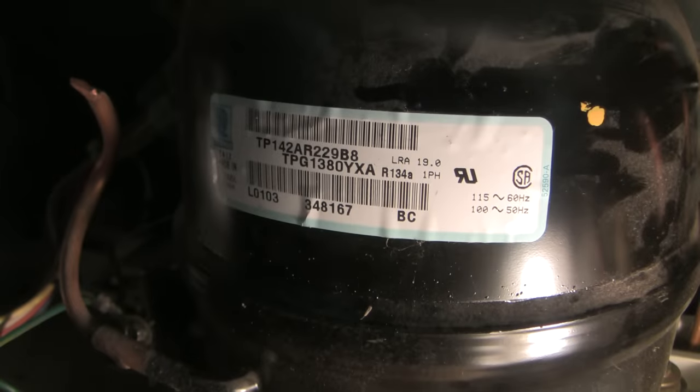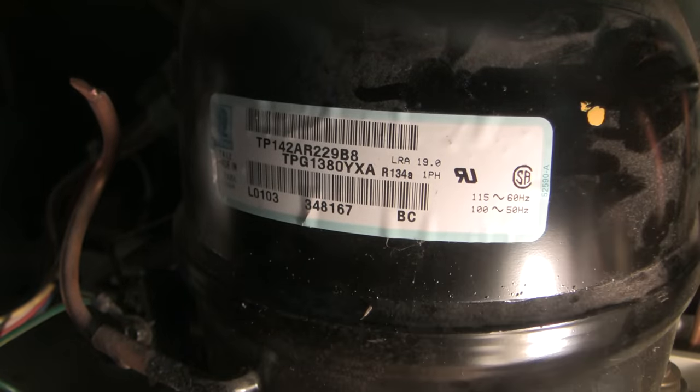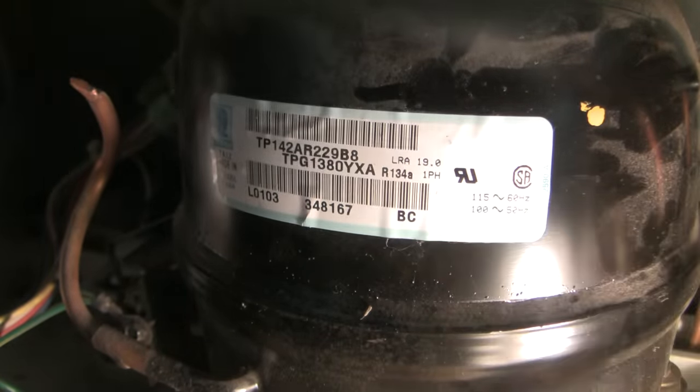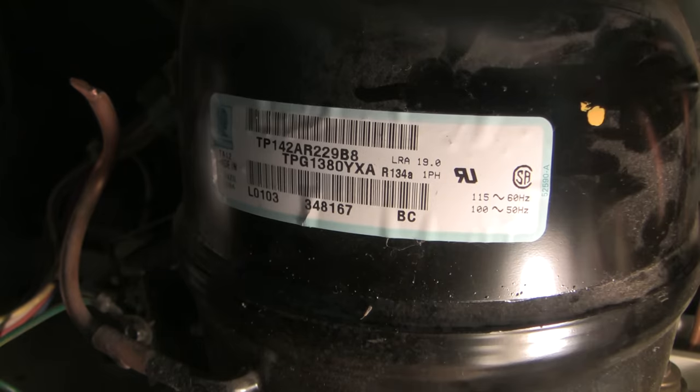Just before we button this up, let's look at the compressor. Made in Brazil, interestingly enough. It's charged with 134a refrigerant and its locked rotor amperage is 19.0 amps.